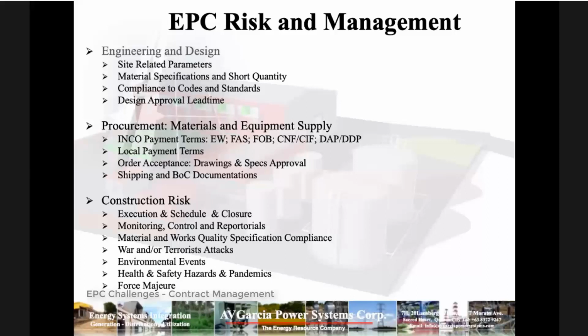Chinese-made circuit breakers too, for example at 69 kV, cannot comply with the 69, 350 kV BIL because their design is only for 66 kV. They can't reach our 350 kV BIL requirement, so they'll deliver you equipment rated for 125 kV BIL instead, 125 kV rated voltage equipment. That's why sometimes the Chinese equipment that arrives is physically much bigger, because of the phase spacing and BIL insulation requirements.